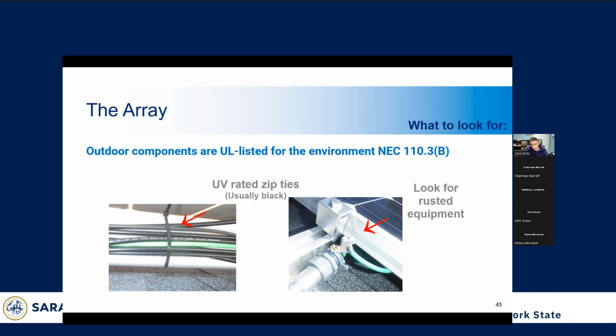All of these systems, or typically PV systems, are rated and warranted for 25 years. So you want all the system components to also last that long. And so I talked about the one on the left. On the right, you can see this lug is starting, the screw is starting to rust. That means it's not rated for outdoor use. Eventually, it's just going to rust through, and it'll likely break apart and come disconnected. And then you have an interrupted ground fault path, and potentially a very hazardous situation. So that's one thing to keep in mind. When you're looking through these systems, if you see screws or ground lugs with a lot of rust, that's an indication that they didn't use the proper equipment.